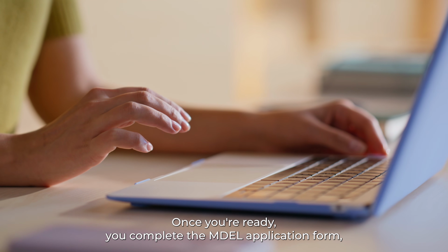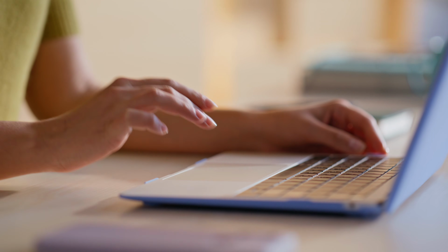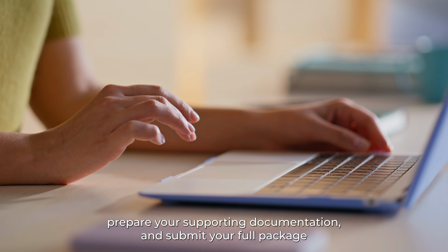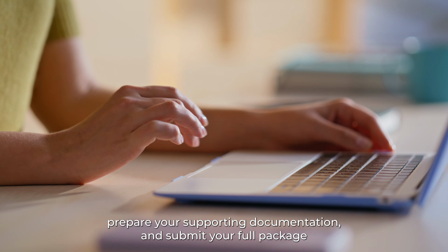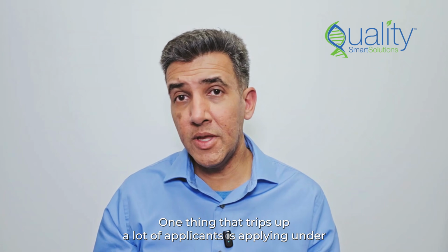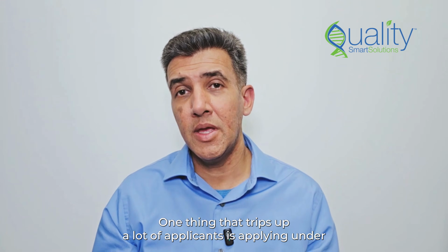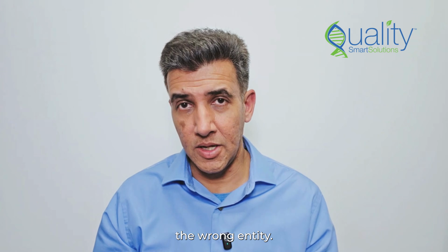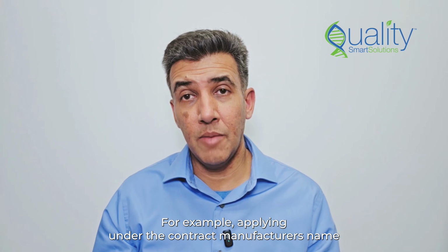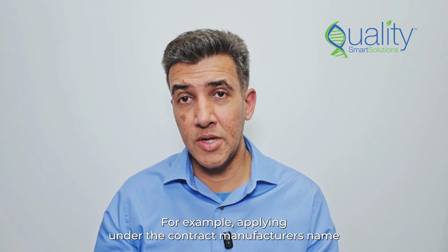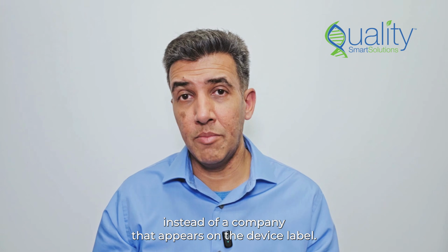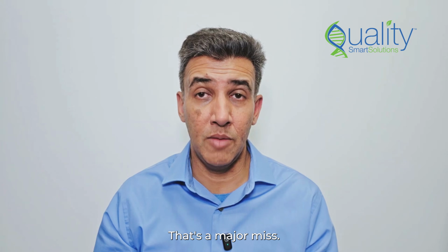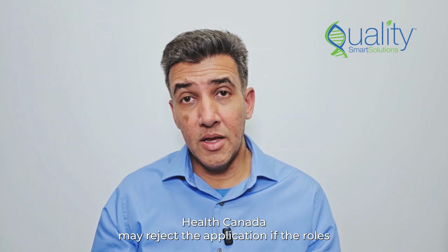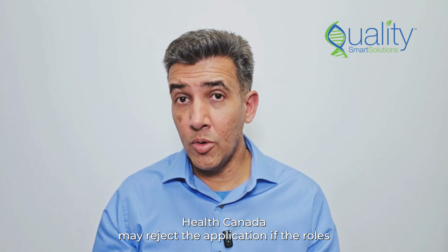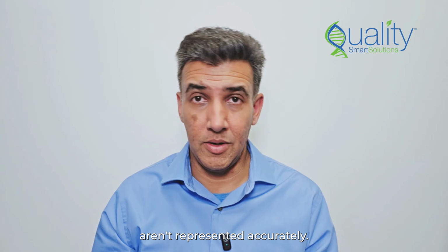Once you're ready, you complete the MDEL application form, prepare your supporting documentation, and submit your full package to Health Canada. One thing that trips up a lot of applicants is applying under the wrong entity. For example, applying under the contract manufacturer's name instead of the company that appears on the device label. That's a major miss. Health Canada may reject the application if the roles aren't represented accurately.